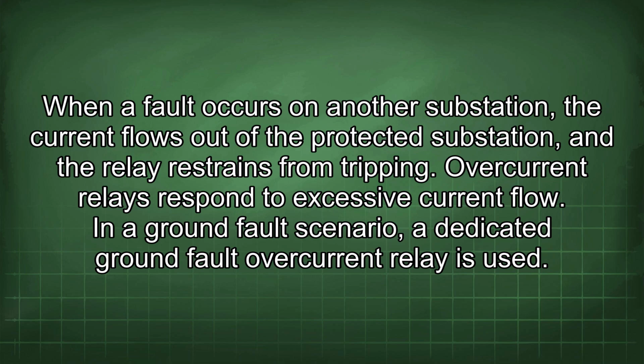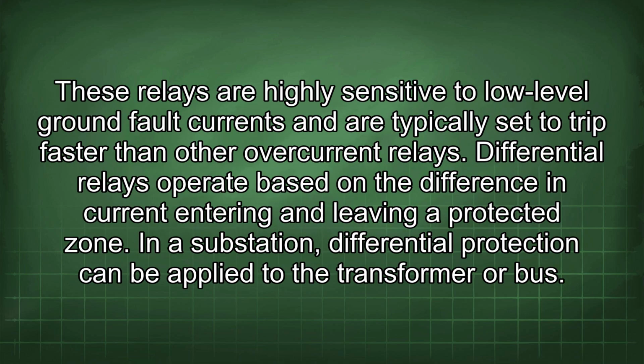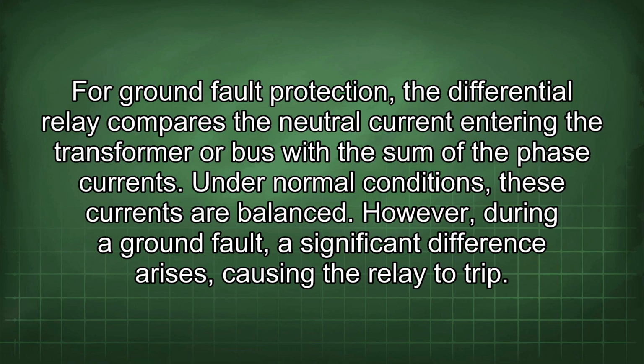Overcurrent relays respond to excessive current flow. In a ground fault scenario, a dedicated ground fault overcurrent relay is used. These relays are highly sensitive to low-level ground fault currents and are typically set to trip faster than other overcurrent relays. Differential relays operate based on the difference in current entering and leaving a protected zone. In a substation, differential protection can be applied to the transformer or bus. For ground fault protection, the differential relay compares the neutral current entering the transformer or bus with the sum of the phase currents. Under normal conditions, these currents are balanced. However, during a ground fault, a significant difference arises, causing the relay to trip.